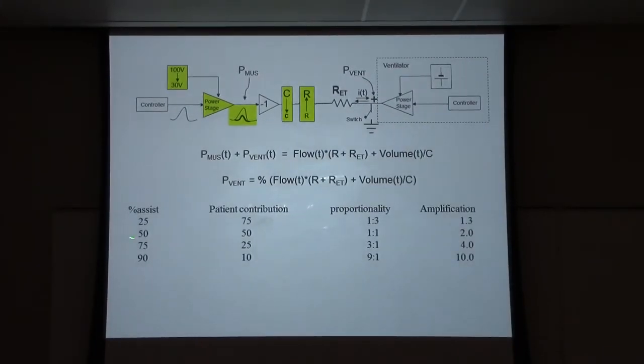If you set it to be 50%, then it's even, 50-50, the proportionality is 1:1. In other words, the ventilator is giving 1 centimeter for every centimeter the patient is giving. And the amplification is 2. At 75%, you get 25 from the patient, 75 from the ventilator, and you're amplifying this solid line by 4 times. So that's how you're saving the patient from having to do it himself, but you're allowing him to be free to control the ventilator.